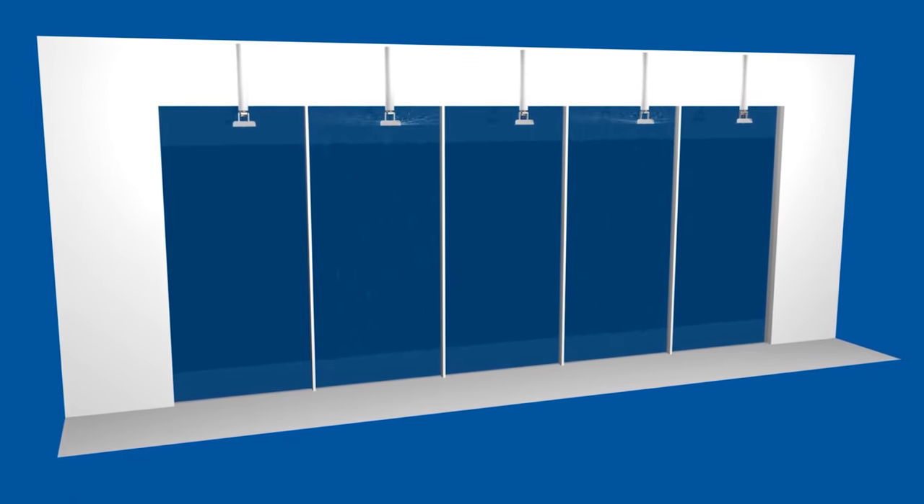So we're trying to find an alternative solution for a window that can be fully operable. We need to think about the worst case scenario where the window is completely opened up. This would result in a window sprinkler just shooting water out through that window and losing most of its effect. Instead, we're looking for a sprinkler head that has a water curtain-like spray pattern, protecting the window from afar and not actually touching it.